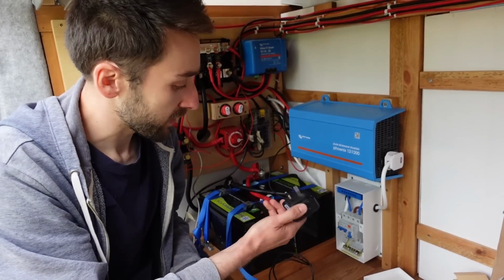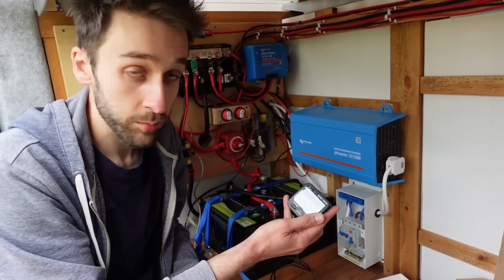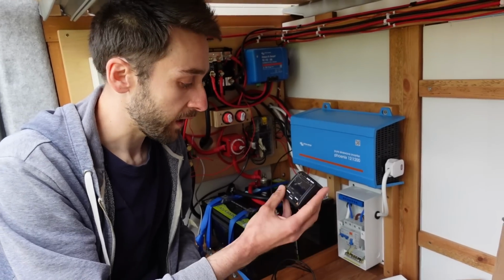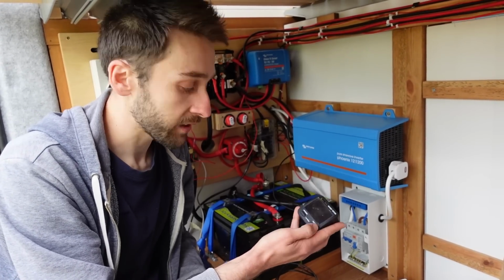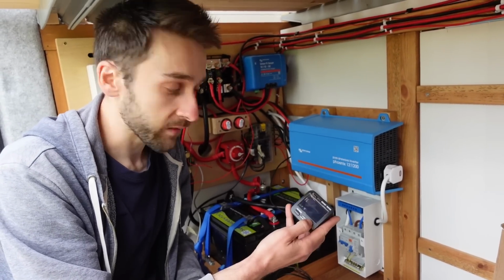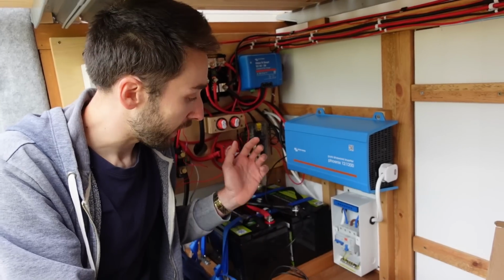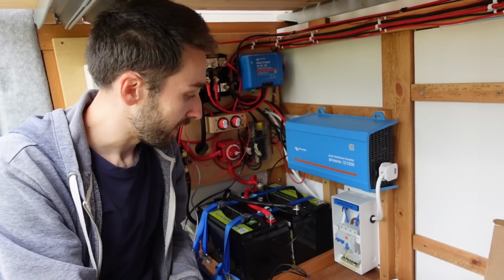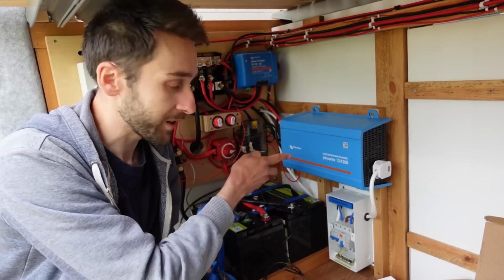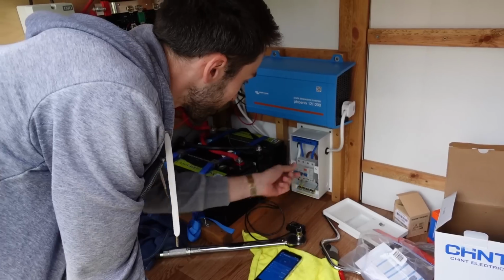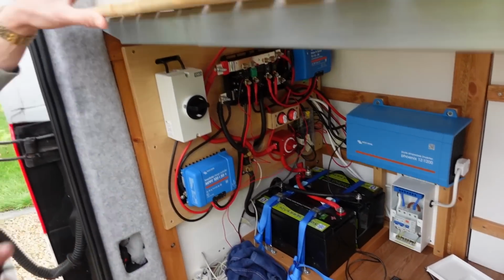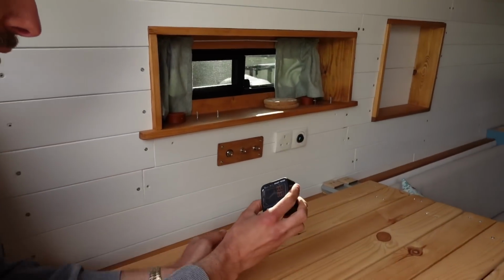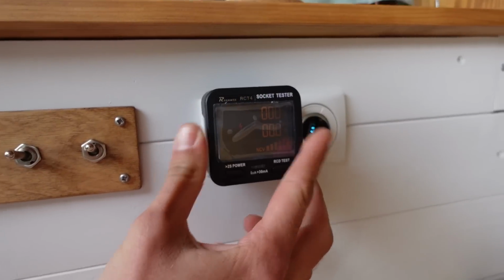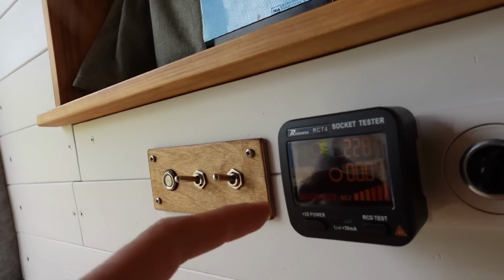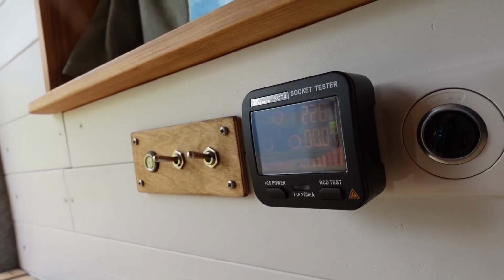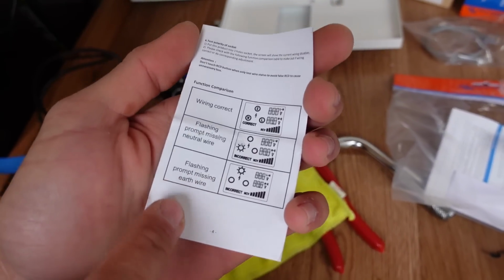You can just plug this in and it tells you if there's any problems with the electric supply, and also allows you to do an RCD test. With that, if we push this button, then it'll actually simulate a fault and should trip the RCD. But we're expecting it not to work because it doesn't have the bond yet. So put that on, and now we can plug this into a socket. It's flashing the top circle, and that means there's a missing earth wire.